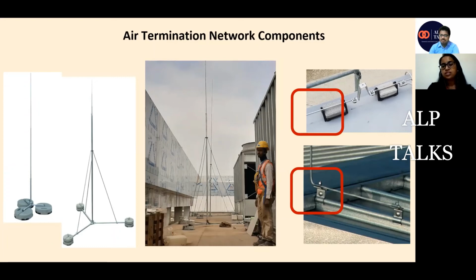For exposed installations, which are open to the atmosphere, we go for aluminium first. If there is a chemically corrosive environment, then we change the material to copper bonded steel or pure copper. Otherwise, we'll go for aluminium only. For buried conductors, like if I am using columns or for earthing, we go for copper bonded steel only, because aluminium we cannot use for underground applications.